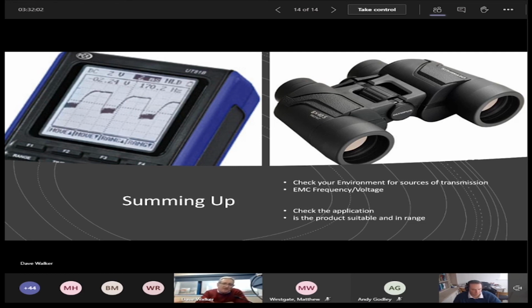What we also do within Detectronic is carry a portable oscilloscope, and that allows us to pick up noise and any interference we might be receiving from electrical background noises, etc. And at the bottom, check the application. Is the product suitable and is it in range for what you're wanting to achieve? Okay, if it's just an on-off, you might get away with it, but if you want that reliable data, that background data, make sure that you're within range. Okay.